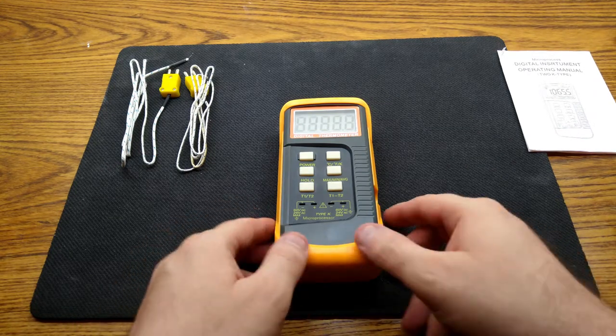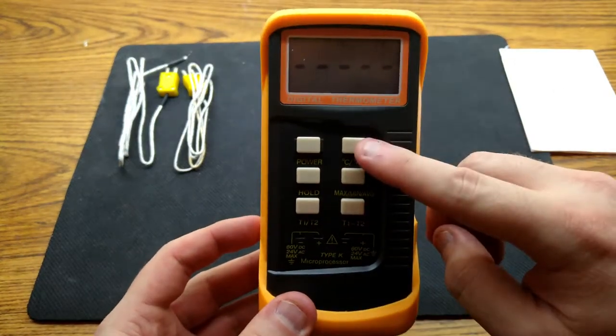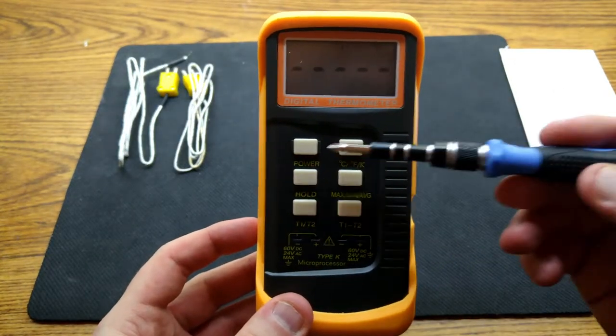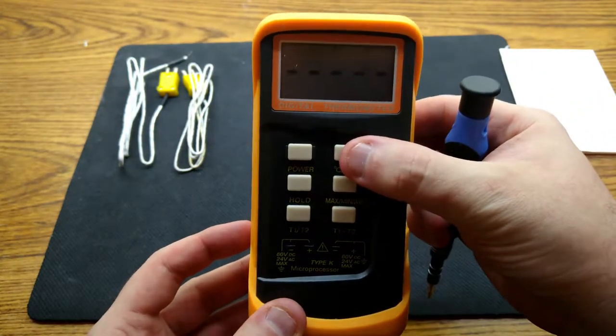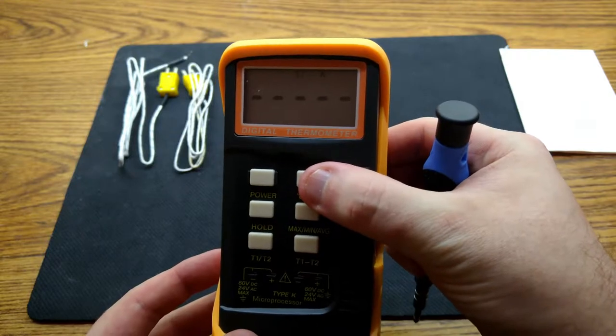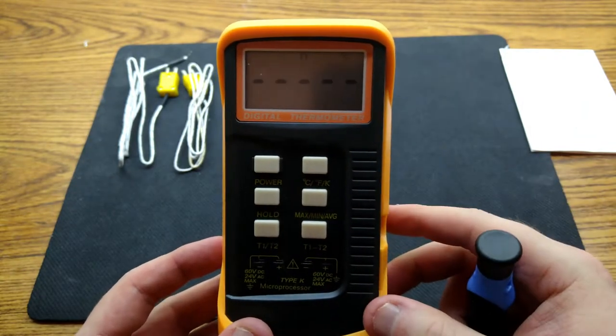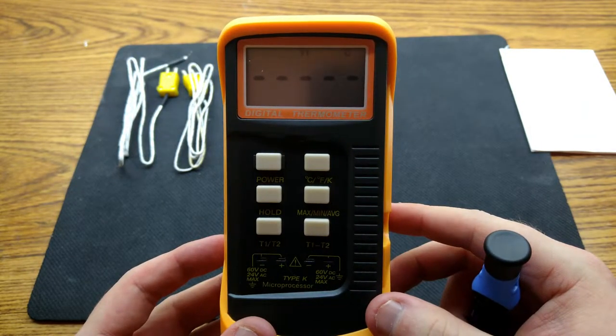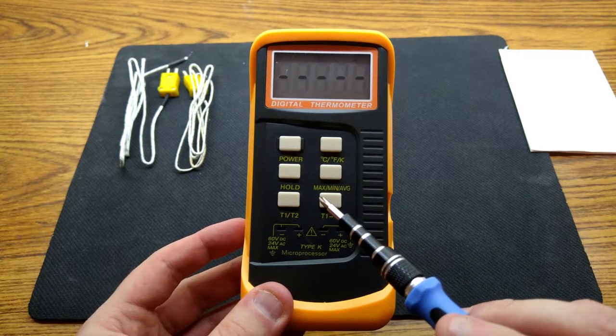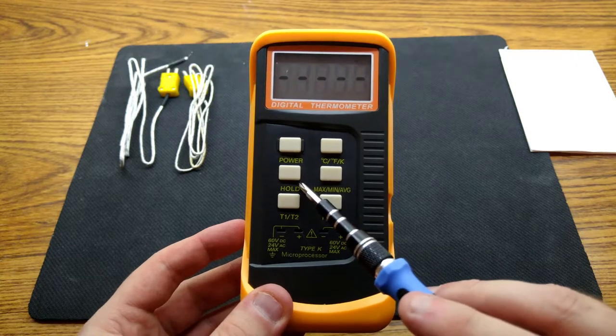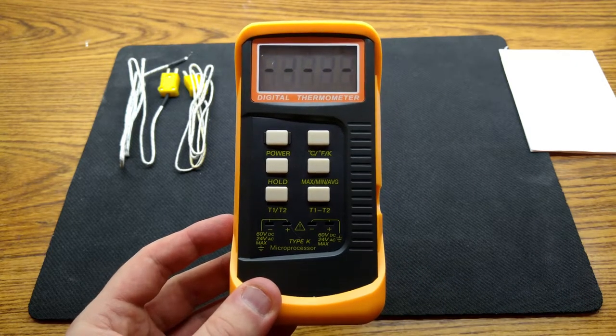The temperature range is claimed to be between negative 50 and 1200 degrees Celsius, which is the normal operating range for a k-type thermocouple. It can display the temperature in degrees Celsius, degrees Fahrenheit, and Kelvin with a five-digit display with one digit for the fractional measurement. The display updates approximately 0.4 seconds. Additional features include max, min, and average and hold.